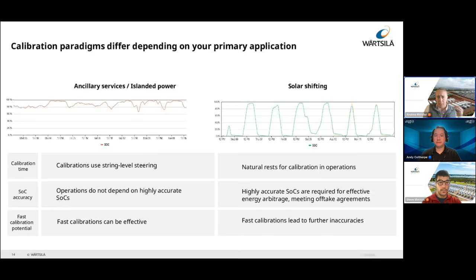At solar shifting sites or energy arbitrage sites, we see more of those natural rest periods, but we also see a need for highly accurate SoCs to effectively perform arbitrage or meet offtake agreements. Fast calibrations we see as less accurate and can often lead to further inaccuracies. So those fast calibrations, 3 to 5 minutes, that some OEM BMSs perform, are honestly throwing off the calibration here.